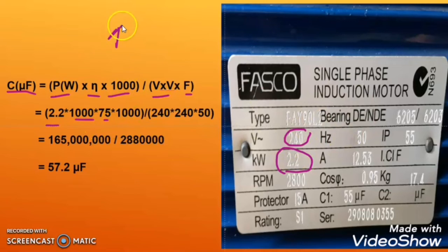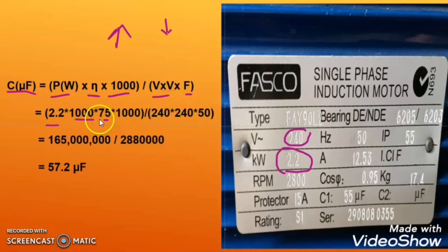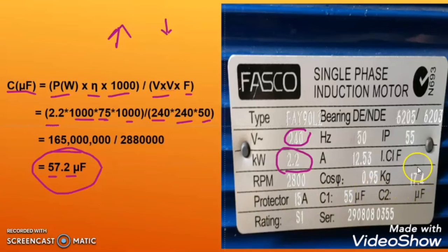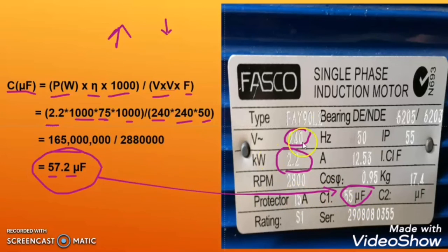Here the efficiency is not given. For a bigger motor, I consider a lower efficiency since the winding is more and the losses will be more, so I take efficiency as 75%. Voltage is 240, frequency is 50 Hz. When we calculate, we get 57.2 microfarad. The nameplate also shows 55 microfarad, so in the market we can use a 55 microfarad capacitor for this induction motor.